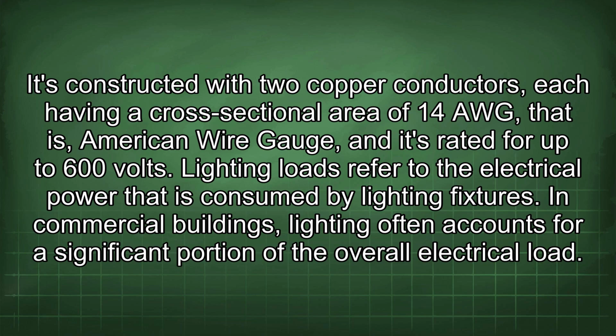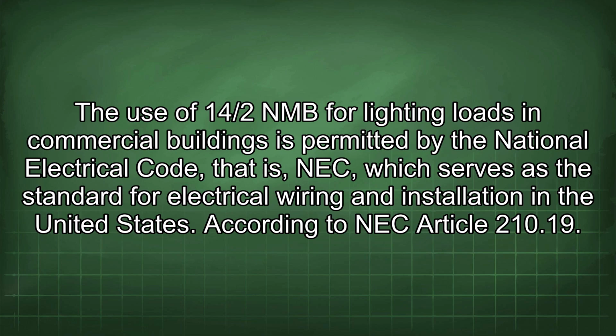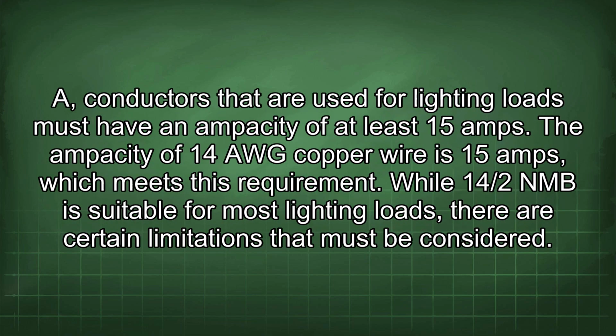Lighting loads refer to the electrical power that is consumed by lighting fixtures. In commercial buildings, lighting often accounts for a significant portion of the overall electrical load. The use of 14/2 NMB for lighting loads in commercial buildings is permitted by the National Electrical Code, that is, NEC, which serves as the standard for electrical wiring and installation in the United States. According to NEC Article 210.19, conductors that are used for lighting loads must have an ampacity of at least 15 amps. The ampacity of 14 AWG copper wire is 15 amps, which meets this requirement.